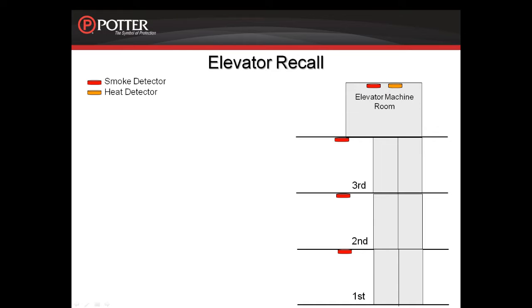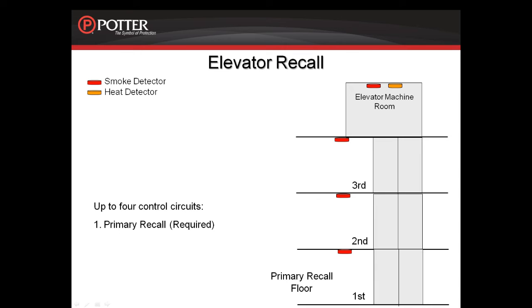Elevator recall pertains to recalling the elevators when the smoke detectors in the elevator lobbies are active. In most cases, the primary floor of egress is the first floor or ground floor of the building. In the event that there is an incident on the first floor, the elevators will recall to the secondary floor of recall, which in this case, as shown on this slide, is the second floor.